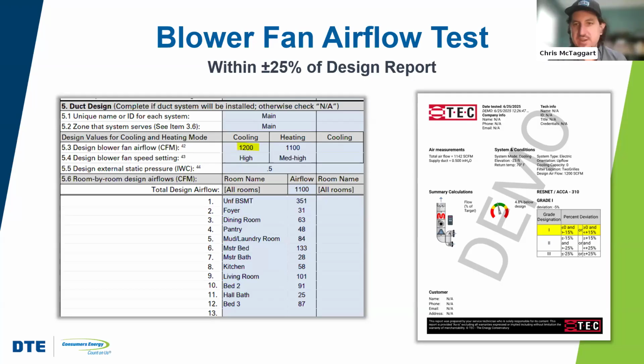But if we take a look here on the right, a test was performed by a rater, and we came out with 1142 CFM. And so that is within 5% less than the design value. So we're still grade 1.